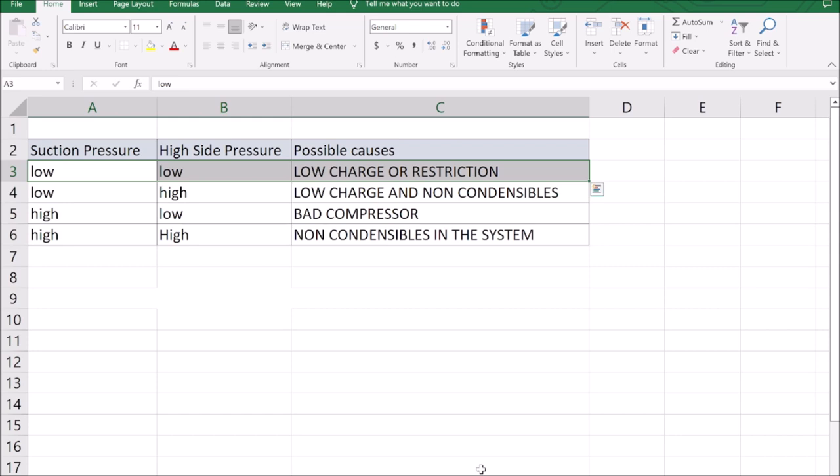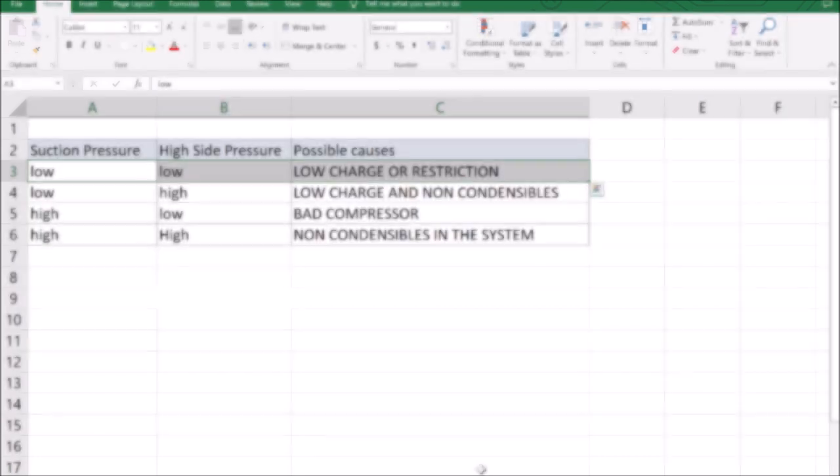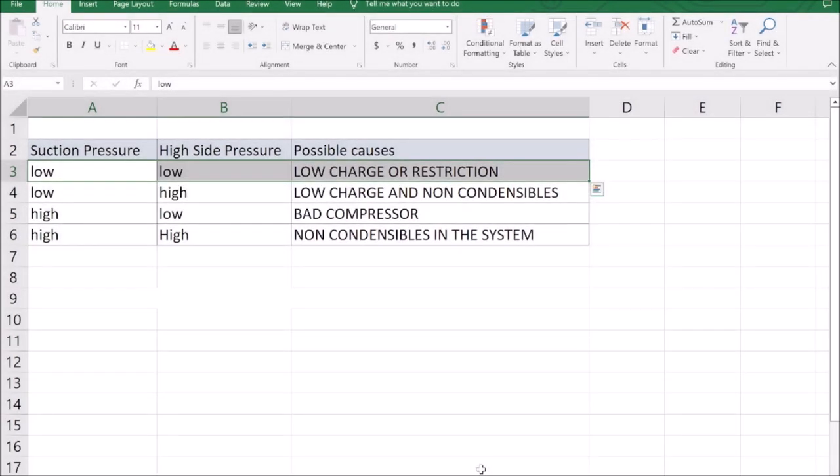So in this case we do not have a sight glass so we potentially have a restriction. So how would we determine if we had a restriction? We would dump in more of the charge. In our case we're using R22, we're probably low anywhere from five to ten pounds. We start dumping in this R22 it could get very expensive if we're low on charge. So this is one of the seldom times you'll see me go hunt a leak before we rule out that we have a restriction. But due to the cost of R22 we just don't have a choice. So let's go, if we don't find a leak then we'll rule out the restriction.